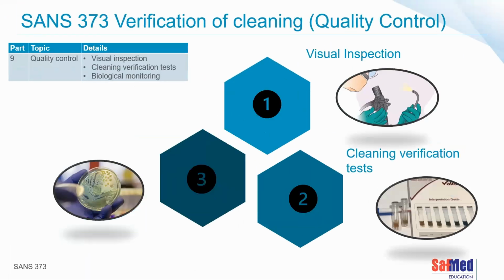In the section on quality control, the standard calls for three things: visual inspection, cleaning verification tests, and biological monitoring. I haven't gone into great detail on biological monitoring today, but there is already a process in our standard for how you should take the specimen and what it should be sent off for to the laboratory. We had a microbiologist's input into that, and we may be adapting it now. If there is an international standard with some changes to it, we're going to review it, see whether it's applicable in our country, and hopefully update and upgrade our own standard around that.